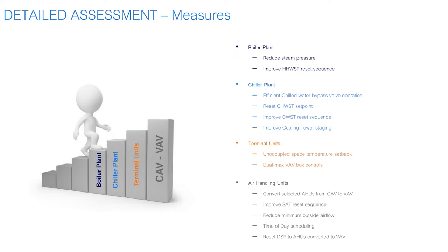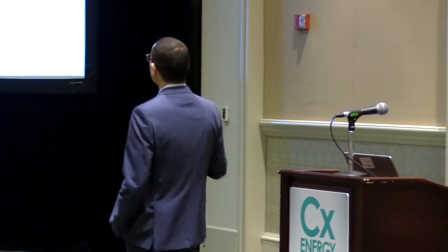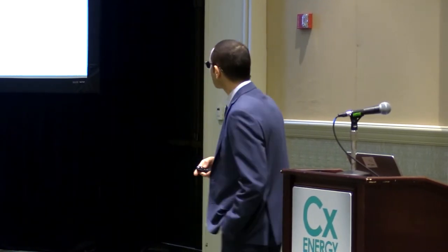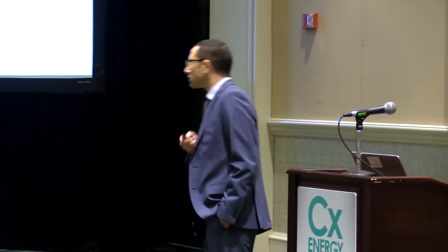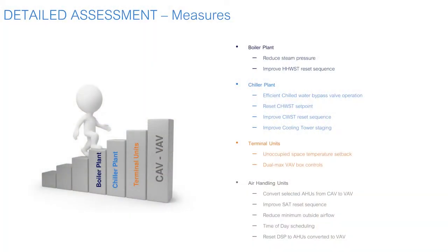There were several categories of measures, and I'm going to show you what they look like. We had measures for the boiler plant to reduce steam pressure, since they were always running very high steam pressures when they didn't need it 24/7. We also had resets on the hot water system. On the central plant, this is a primary constant volume chilled water system with a bypass valve. The bypass valve, from the beginning, was always constantly open at 45% or more, so they were putting all these chillers online and circulating the water back to them. That indicated a huge opportunity for more efficient chilled water bypass valve operation, resets on the chilled water, condenser water, as well as more optimized cooling tower staging.